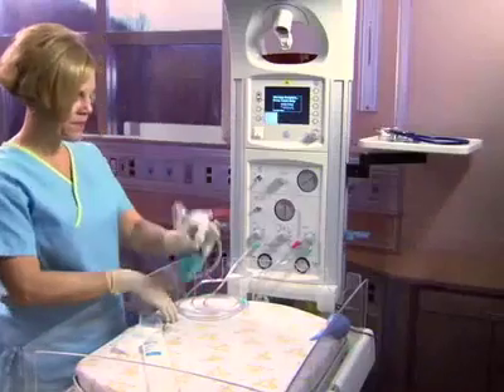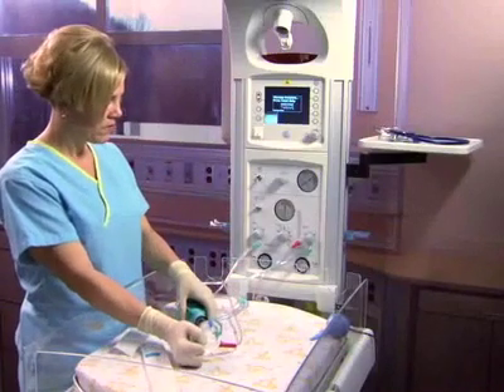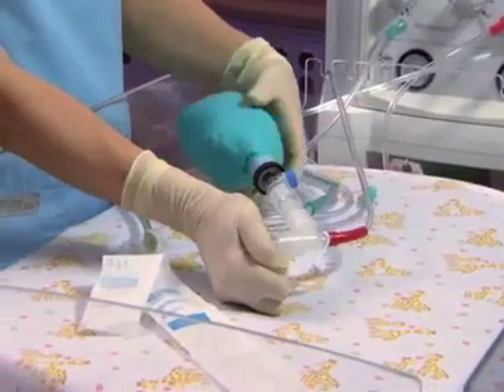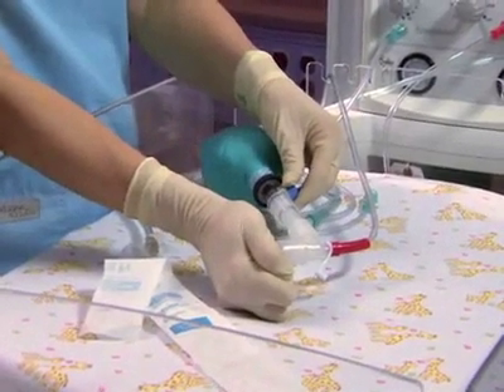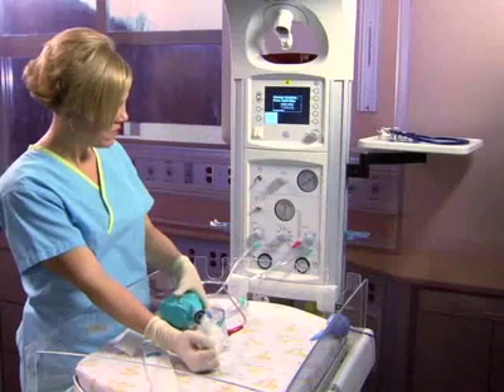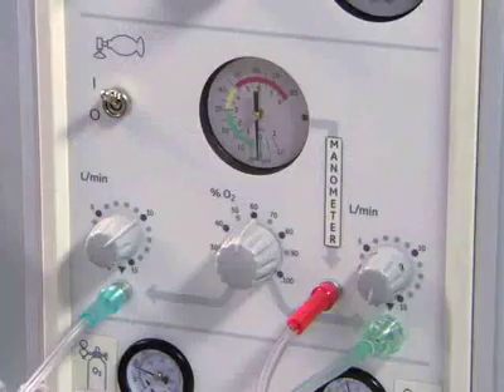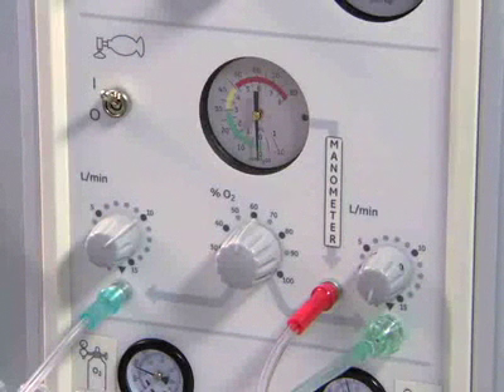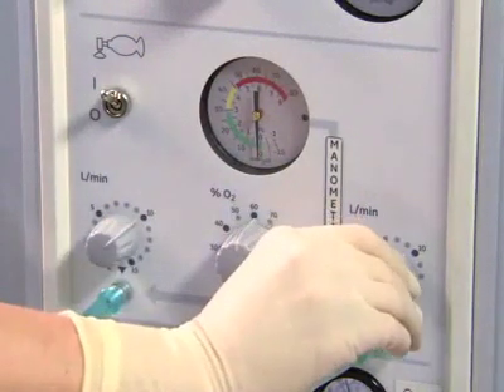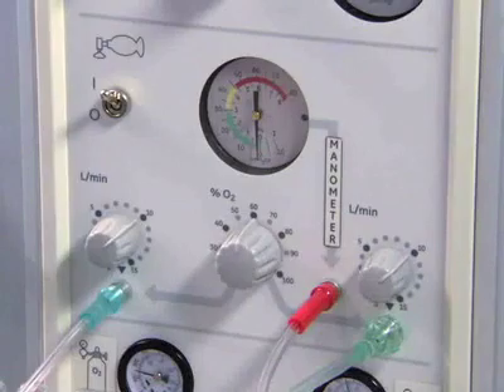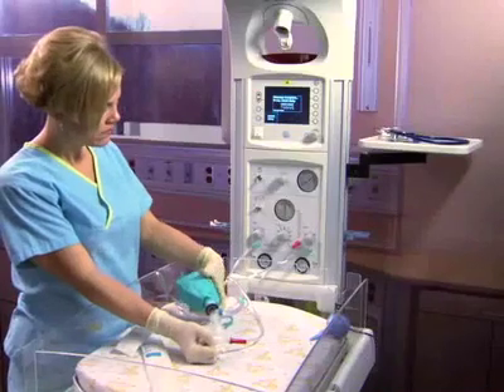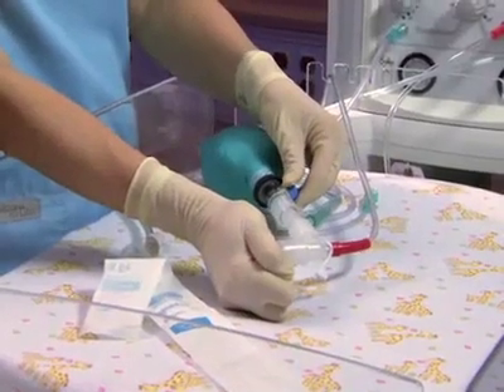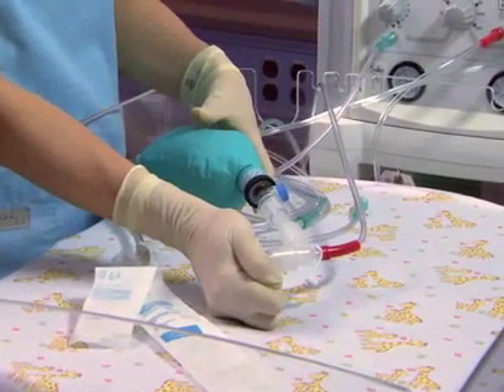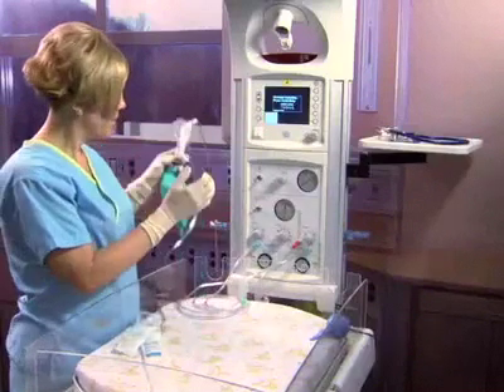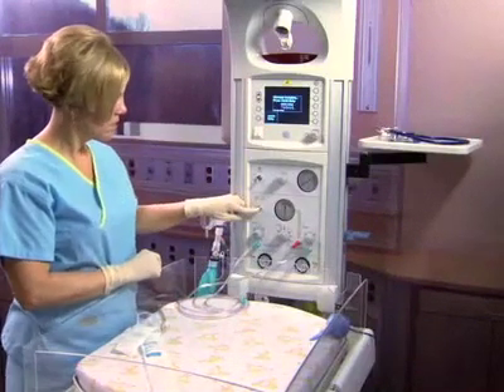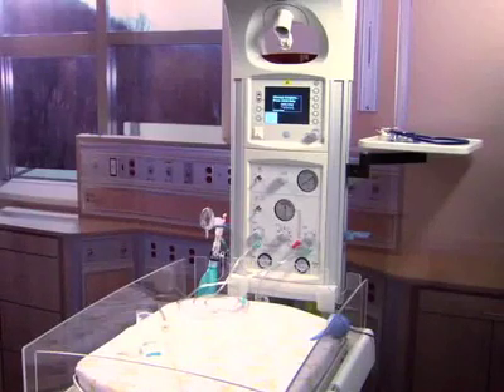Follow hospital, regional, or national guidelines for setup of your manual resuscitator. Common steps might be to occlude the patient connection port or face mask of the manual resuscitator and set PEEP and PIP on the manual resuscitator. PIP and PEEP may be adjusted by changing the flow rate using the flow meter control knob on the front panel of the resuscitation system. It may also be adjusted using the PEEP valve on the manual resuscitator, depending on the type of resuscitator system that is connected. Turn the medical gas switch off until ready to initiate resuscitation or airway support measures.